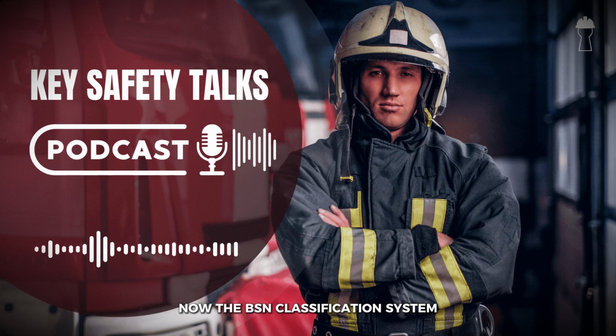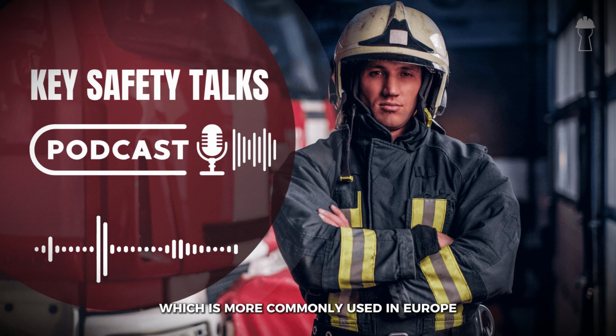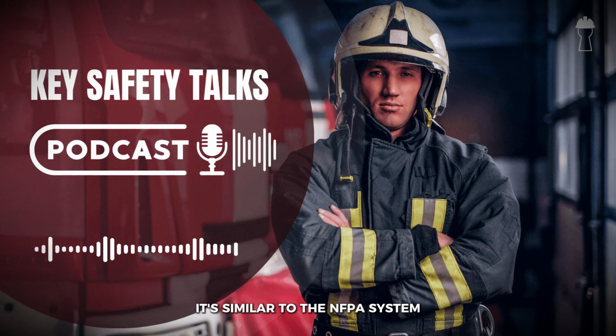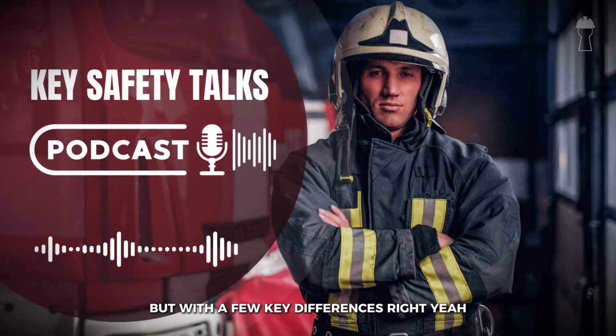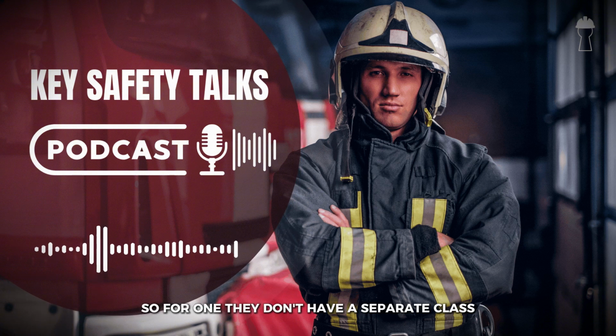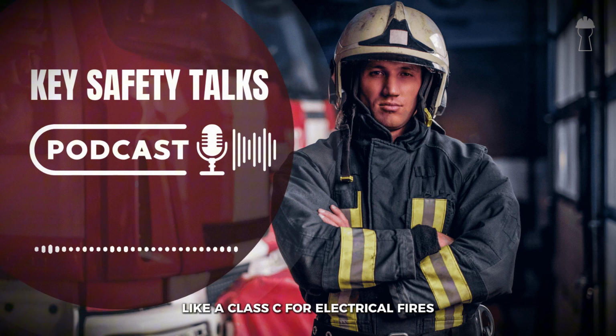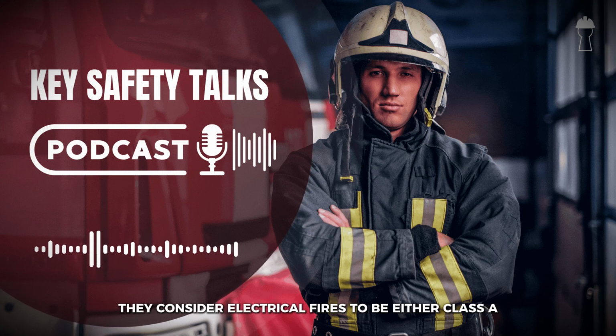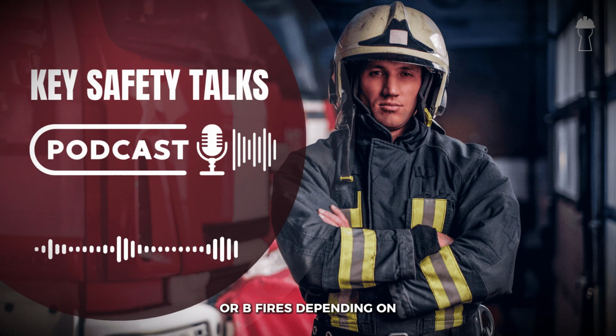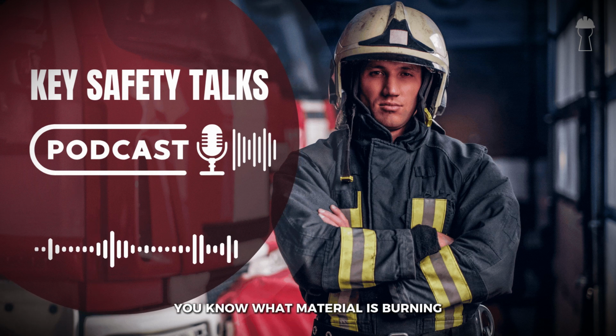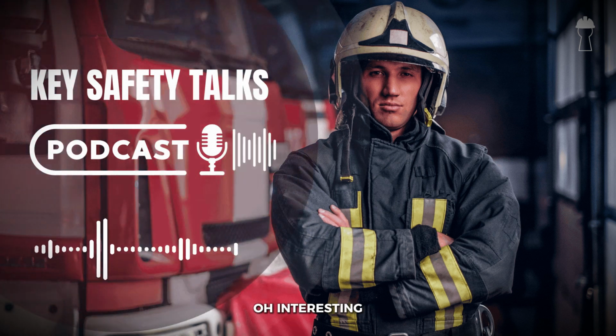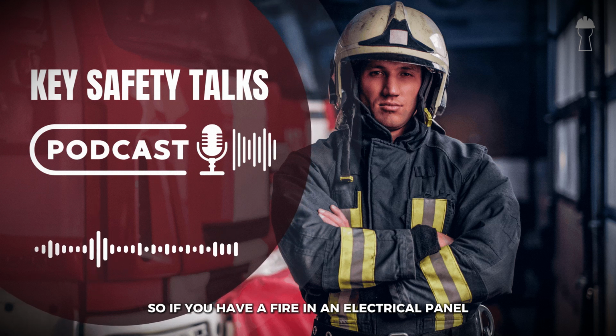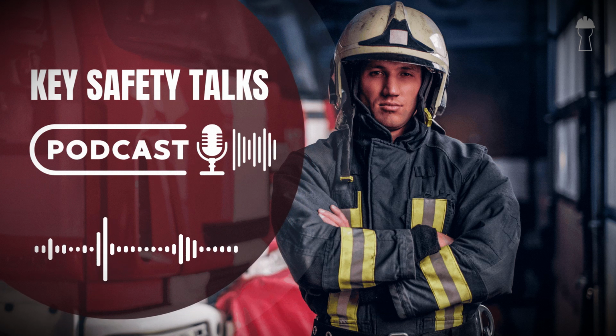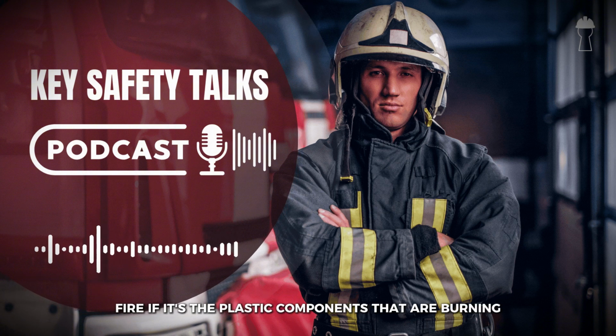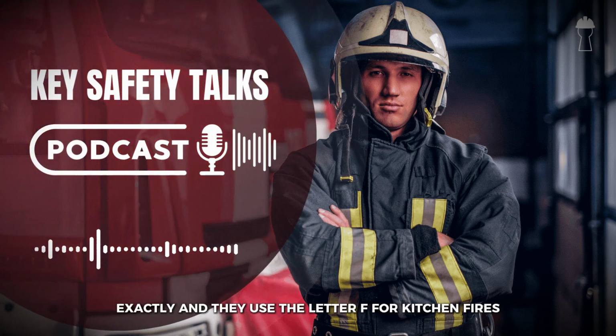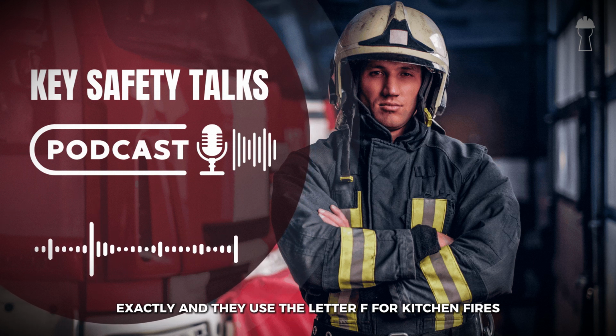Absolutely. Now, the BSEN classification system, which is more commonly used in Europe, it's similar to the NFPA system, but with a few key differences, right? Yeah. So for one, they don't have a separate class, like a Class C, for electrical fires. Instead, they consider electrical fires to be either Class A or B fires, depending on what material is burning after the electricity is cut off. Oh, interesting. So if you have a fire in an electrical panel, once you disconnect the power, it could then become a Class A fire if it's the plastic components that are burning. Yeah, exactly. And they use the letter F for kitchen fires instead of K.